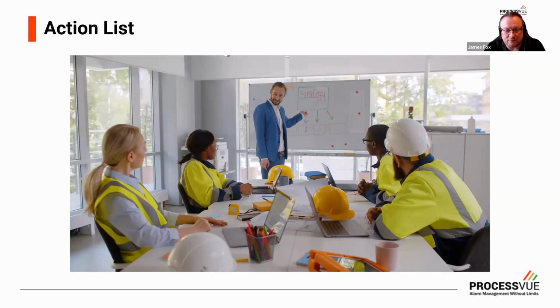It could be that you need to update documentation to reflect the changes that have been made to those alarms. It could be that we need to update P&ID drawings as well, based on the changes that we've agreed. So out of each rationalization session comes a series of activities and tasks that have to be completed on a regular basis. For example, if we've got to make those 50 changes to the alarms, we're adding on delay timers.